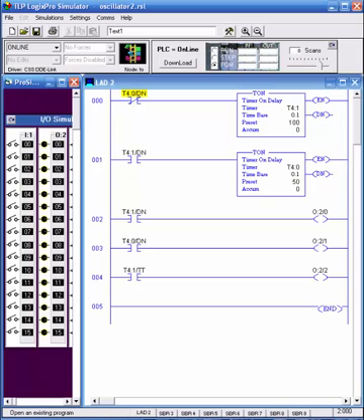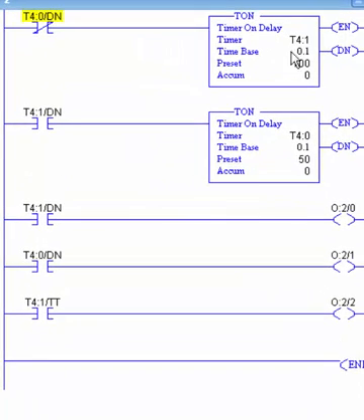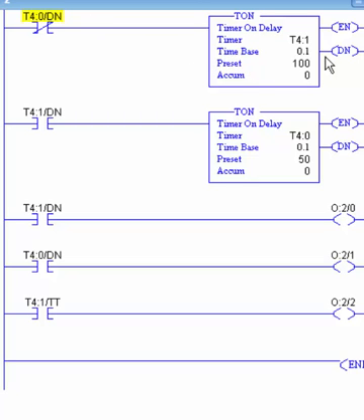Another timer application I want you to look at is an oscillator. From digital logic you know it's often required to have an oscillator at some given period or frequency. I've got two timers here: T4:1 is set at 10 seconds and T4:0 is set at 5 seconds. To get this oscillator working, we're going to oscillate back and forth between these timers. The first timer T4:1 is driven by the done bit of T4:0.